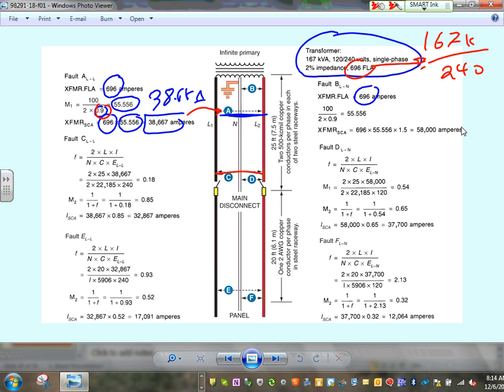Now go downstream to C. This is the second calculation, at C. Now I pulled conductors, guys, and when you pull the conductors, they're going to choke the current. The way they calculate it, here we have 25 feet of two 500 kcm copper conductors per phase, each in steel raceways. Then 25 feet will choke the current.